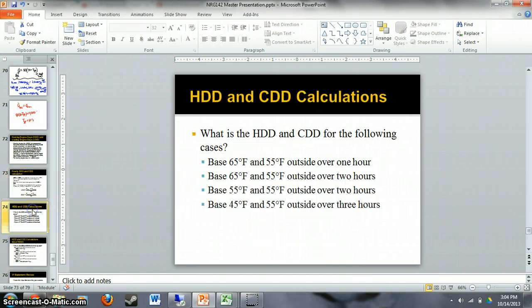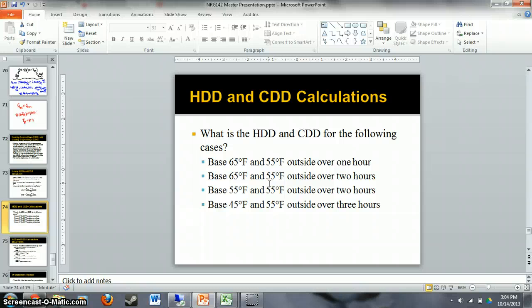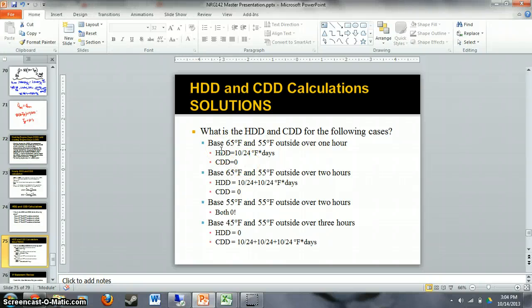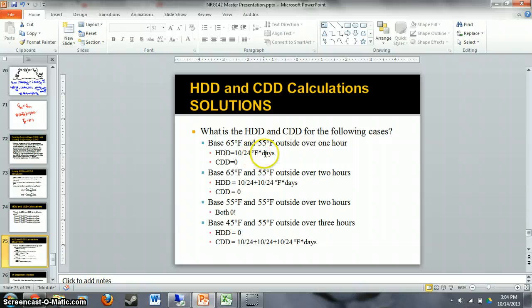Let's look at an example. We're going to calculate heating degree days and cooling degree days for the following cases, using 55°F as our outside temperature. For a base of 65°F and 55°F outside over one hour, cooling degree days is negative, so we set it to zero. Heating degree days is the temperature difference of 10 degrees divided by 24, giving units of degree-Fahrenheit times days.